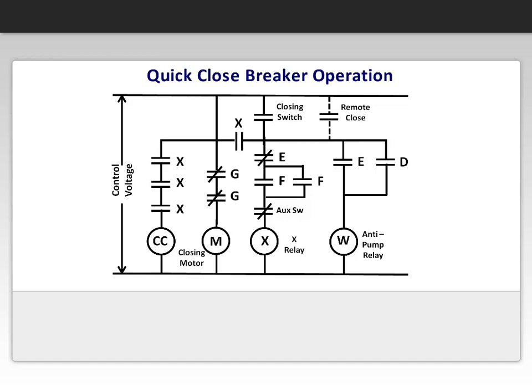Here are some typical examples of the dynamic illustrations used in the Training to Go modules. Let's now go over the operation of a quick close breaker and see how the diagram works. With the control voltage applied, the motor is energized through the G-switch contacts and charges the closing springs. When the springs reach the fully charged position, the mechanically operated switches change state. When the switches operate, the G-switch opens and stops the motor and the F contacts close, preparing the breaker for the closing operation. Next, the closing signal from either a closing switch on the breaker cover or from a remote push button or a secondary device energizes the X relay. Next, the closing relay CC closes.